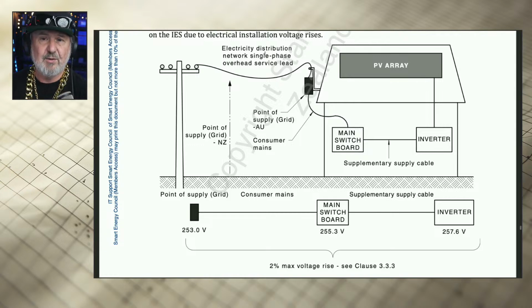But there's one other thing that really helps reduce voltage rise, which I've already mentioned: keeping the cable length short and the conductive area large. The bigger the cable, the less the voltage drop — once again, Ohm's law. So what you're looking at now is 4777 Part 1, and the requirement is no more than 2% voltage rise from the point of common coupling to the output terminals of the inverter. It's not much — in this case it's showing 253 volts at the grid connection point, and the inverter's at 257.6. So there's your 2% max.